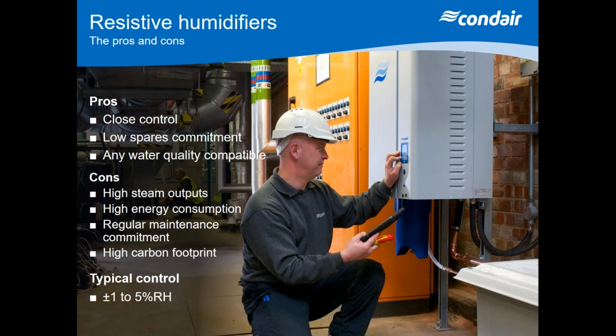Now we're going to look at the resistive heater humidifier, which is another electric humidifier. Now, this is very, very simply a bit like your kettle at home. It's going to have a heater element inside a stainless steel boiling vessel. Albeit it's going to be a lot more sophisticated in terms of how it operates, because it's going to have a number of elements in there. And the main benefit of these units is you can burst fire the elements to give you really tight, fast control, which you wouldn't get with the electrode boiler, because you're just relying on current draw, which is going up and down very slowly. So with these resistive units, you can get close control, plus or minus 1 to 5%, depending on the design of the system and the temperature range as well.